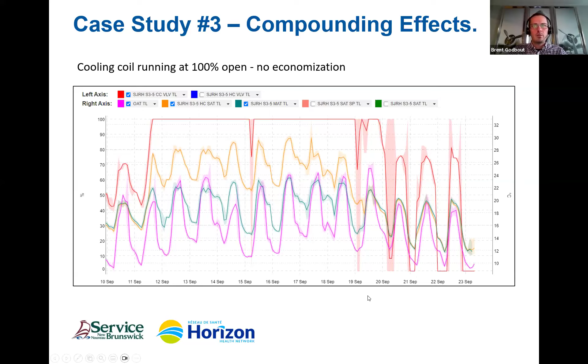I think the next one zooms in. Yeah. So here's the end of that passing heating coil valve. So we're still passing on the heating coil valve. Our cooling coil is screaming at 100%. Then we fixed that passing heating coil valve, and boom, at nighttime. And here's this purple line, which is actually our temperature line. So you can see our temperature was dropping down to 12 degrees, 10 degrees overnight.